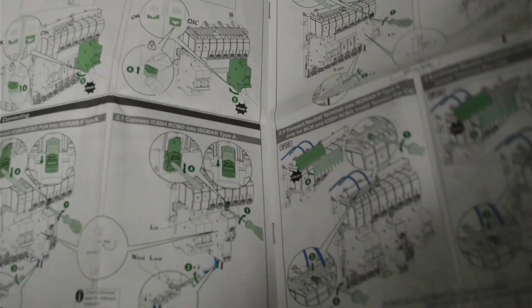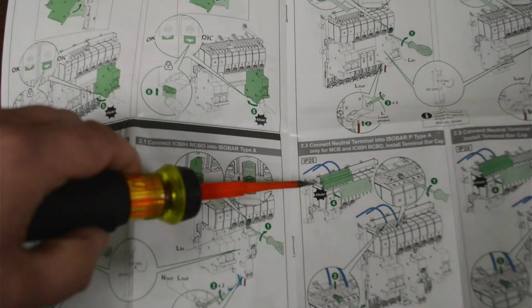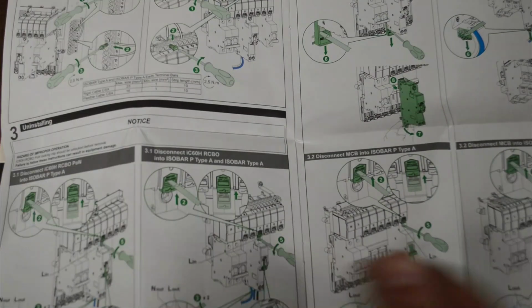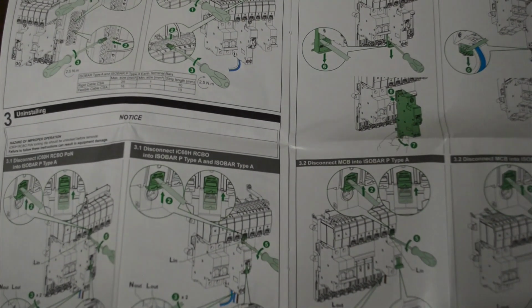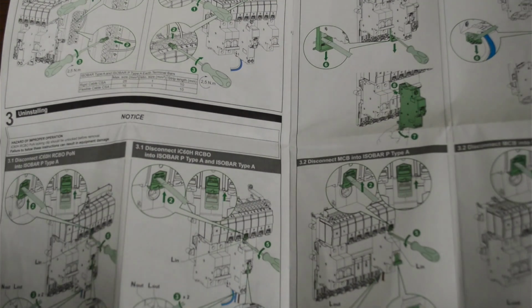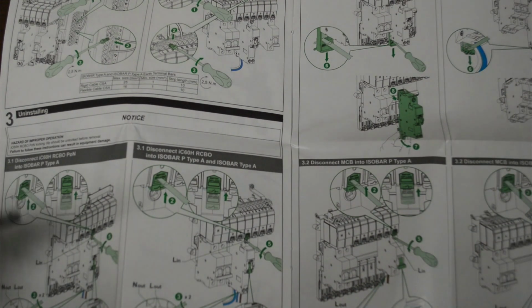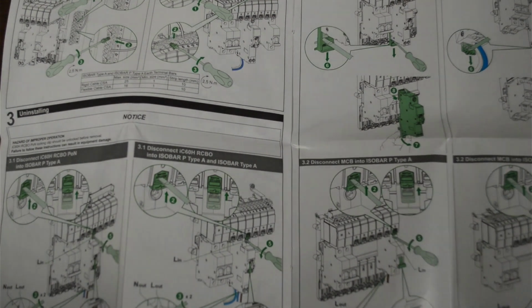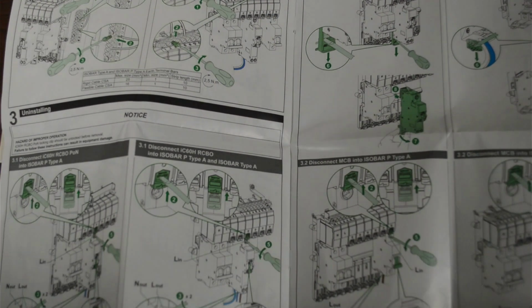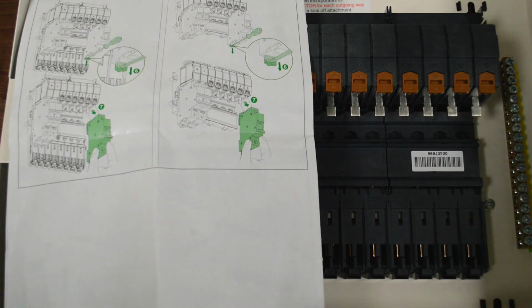It's all quite interesting. It is good, you can cover up your neutral bars. They come with all these in the boards, so they're trying to make it so there's no exposed terminals or bits of metal or copper, brass, whatever inside the enclosure itself. So in the event it is open while it's energized, the risk is as low as possible, which helps us as installers and people carrying out maintenance endlessly.